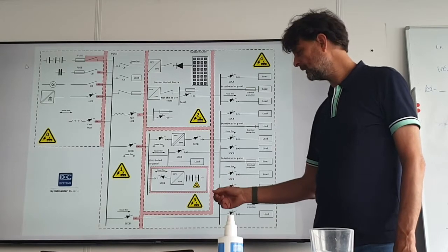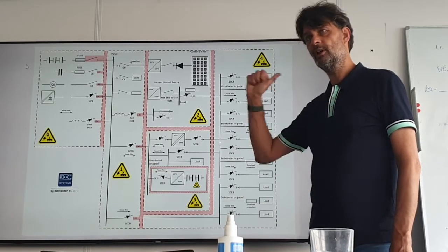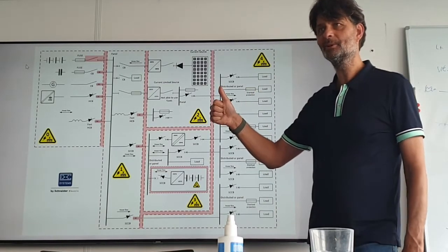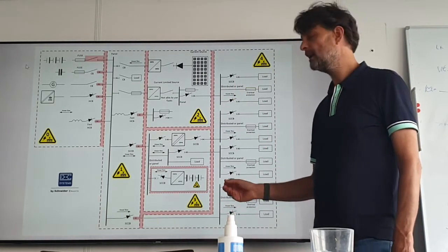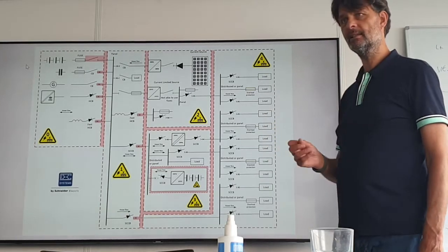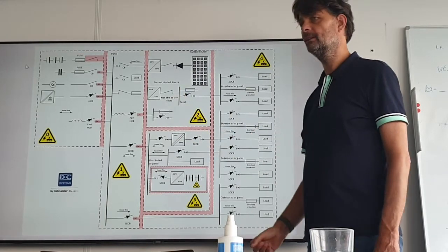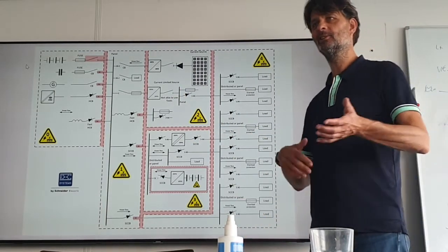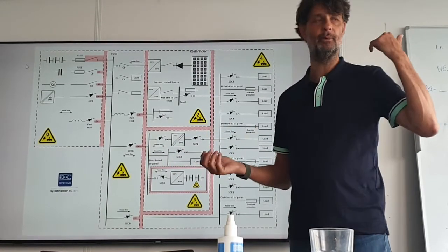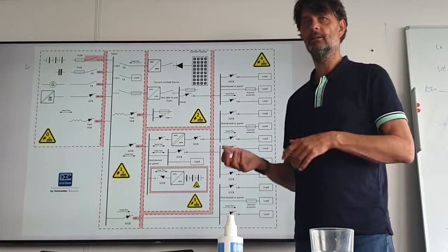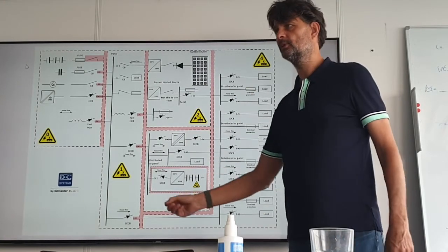And for streetlights, we could even put it to 10 milliamps. So that means if somebody is there to touch, and it's not his last day anymore, we are on the conservative side. And that's how we manage to get these specifications, which don't exist in the IEC, into the Dutch standards. And therefore, instead of a license to kill, we get a license to operate. So we get the possibility to have the ABN building, the Pulse building, the street lights, start building these installations without product standards, but with installation rules.